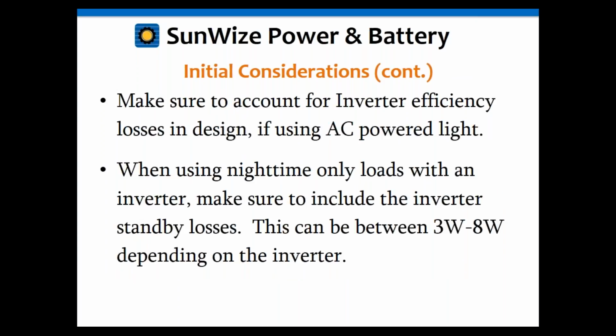Okay, getting back to the AC nature again, if you are going to have an AC light, make certain you include the inverter inefficiencies in the losses design. Most inverters are somewhere around 85 to 90% efficient, so you need to add an extra 10 or 15% to the load to compensate for that inefficiency.